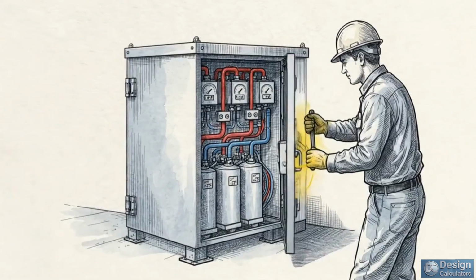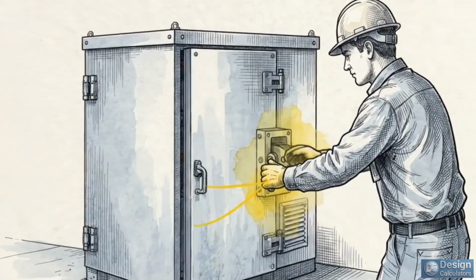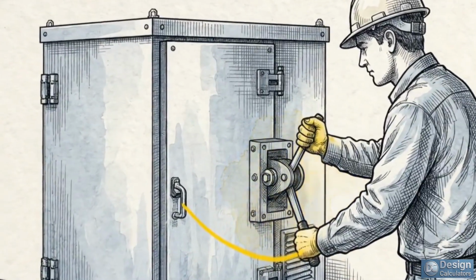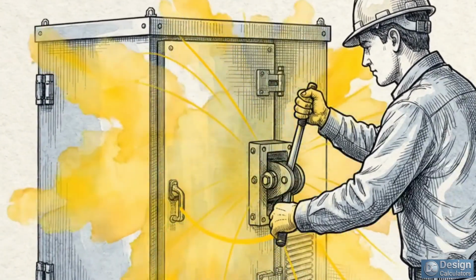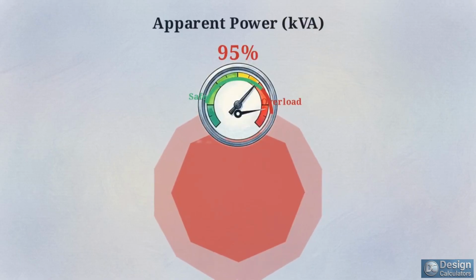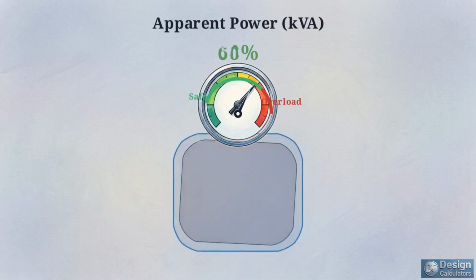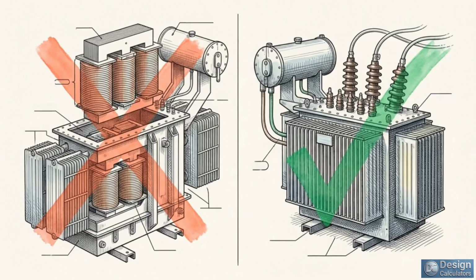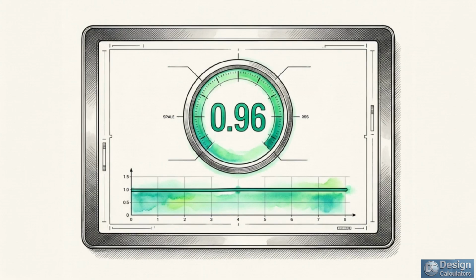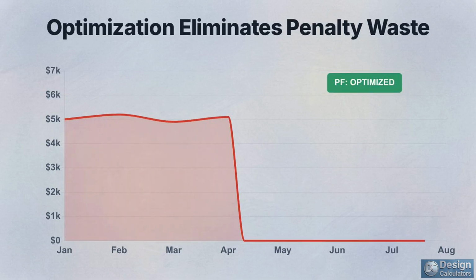Factory B eventually addressed its current issues by installing an automatic capacitor bank. Their voltage stabilized instantly, and the monthly utility penalties disappeared. By shedding the excess current, the facility unlocked significant amounts of spare capacity in their existing transformers. They gained the equivalent of a heavy infrastructure upgrade without actually replacing any primary hardware. Tracking power factor is one of the most critical health indicators for any electrical system. Optimizing it prevents expensive financial and physical waste.